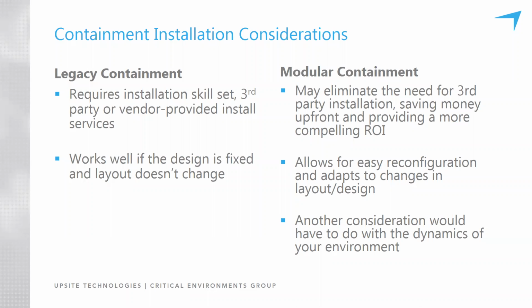Let's talk about a dynamic environment. So will your cabinets or aisles and containment design remain permanent for the foreseeable future, like it's a fixed design, and all you're going to be doing is moves, adds, and changes within the racks that are already permanently in place? Or are you going to need to plan for reconfiguration and layout changes as your demands change? So these types of strategies for going forward into the future and how you might evolve your room often dictate or point you in a direction as to what options you might have from a containment methodology.